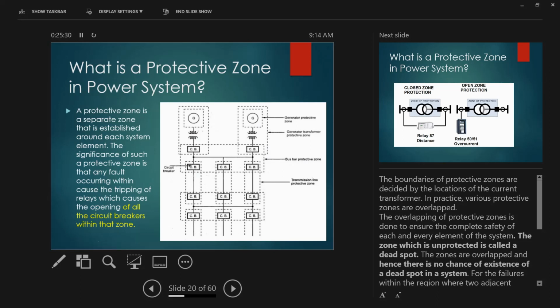If the bus tie is open and there is a bus trip over here, it doesn't trip the other bus. If the bus tie is closed, there are some kind of inputs to the bus differential so that it will trip bus A and bus B. So something like that. There's a lot of logic schemes that I think in our days today are very flexible. But that's the zone protection of the power system.